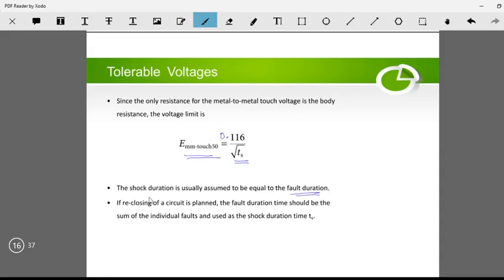If reclosing of a circuit is planned, then the fault duration time should be the sum of the individual faults and used as the shock duration time. With reclosing facilities, there could be a fault in one period, then it opens and recloses, and the fault continues, opens, recloses, and so on. So you have to consider the sum of all these as the shock duration.